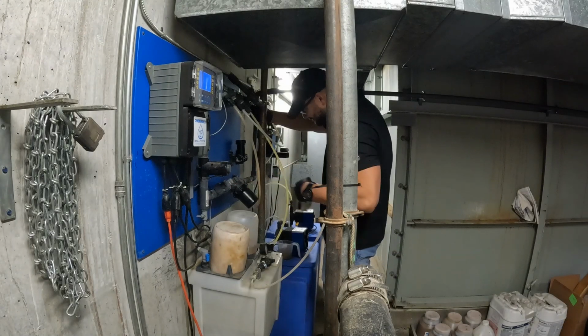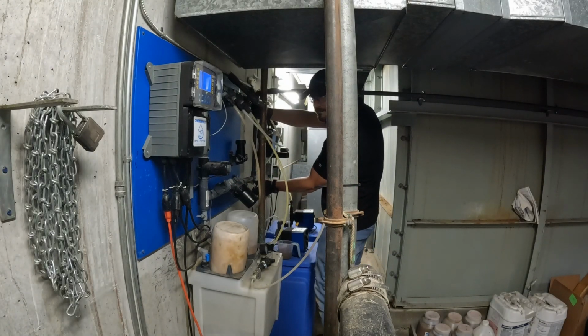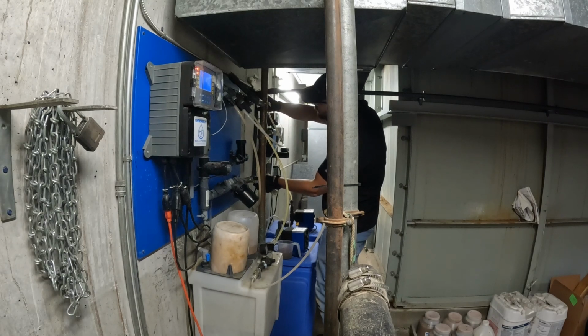Once everything has been inspected and cleaned, you can bring the flow back to the manifold. Be sure to close the sample nozzle before opening the ball valves.